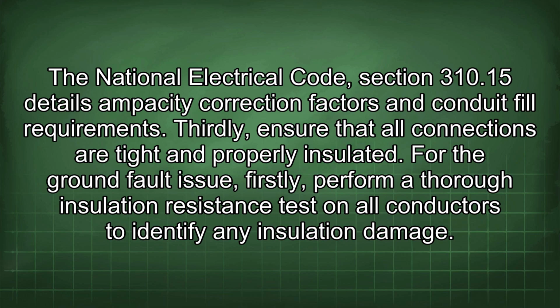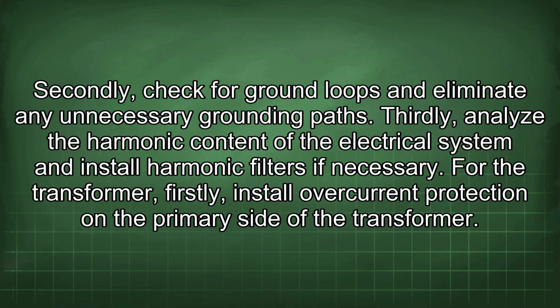For the ground fault issue, firstly, perform a thorough insulation resistance test on all conductors to identify any insulation damage. Secondly, check for ground loops and eliminate any unnecessary grounding paths. Thirdly, analyze the harmonic content of the electrical system and install harmonic filters if necessary. For the transformer, firstly, install overcurrent protection on the primary side of the transformer.